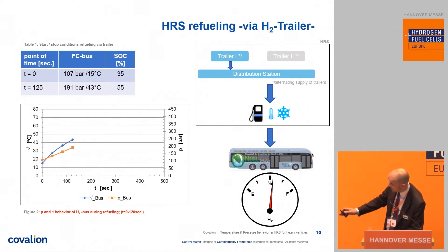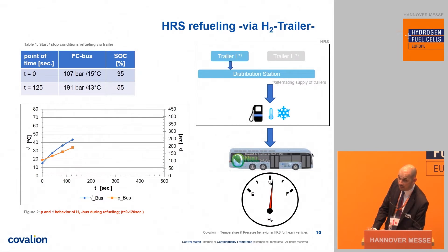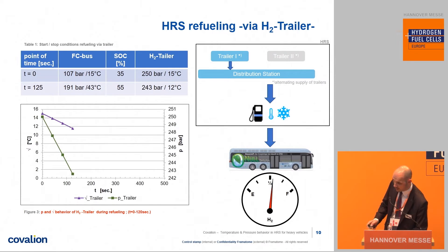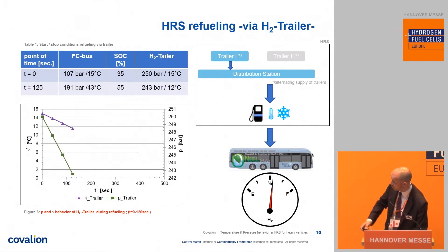You can now see the temperature and pressure behavior in the fuel cell bus. There is always a stop criterion — for example, pressure, temperature, or mass flow. After about 125 seconds, one of the stop criteria is reached, and the software again checks which is the most efficient way to continue refueling. Let's also look at the behavior in the H2 trailer — you can see the pressure and temperature drop in the trailer during the refueling of the bus.